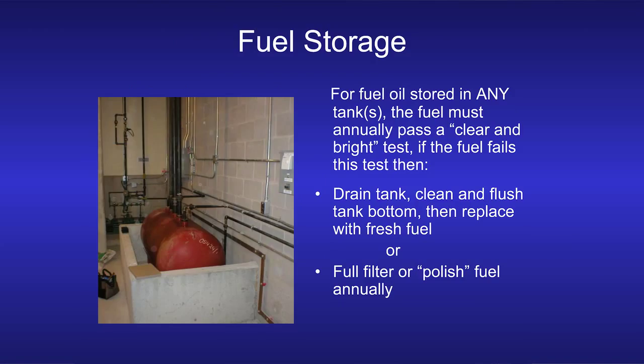Fuel storage: the fuel must pass an annual test. We extract a sample from the bottom of the tank, farthest away from the fill port if possible. So that's the worst possible sample we could get out of your tank. And we take a look at it, and if we can't see through it like this glass of water, you have a problem.